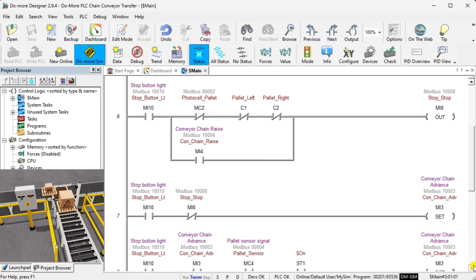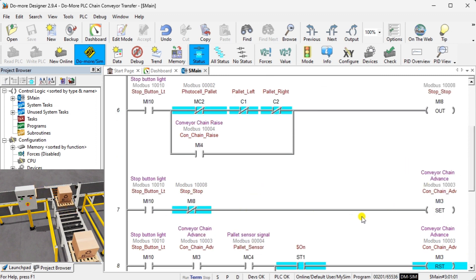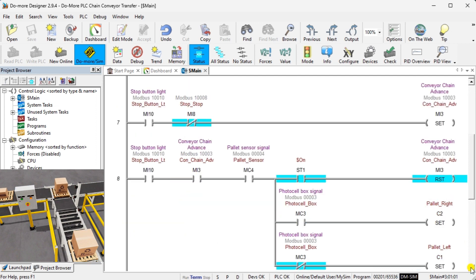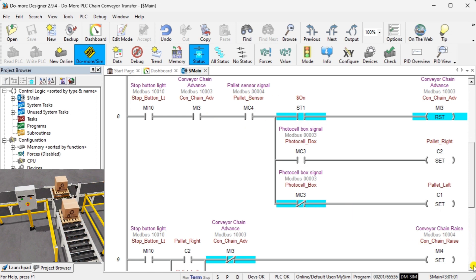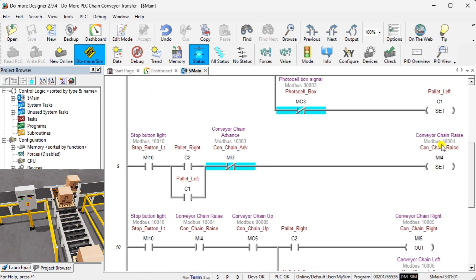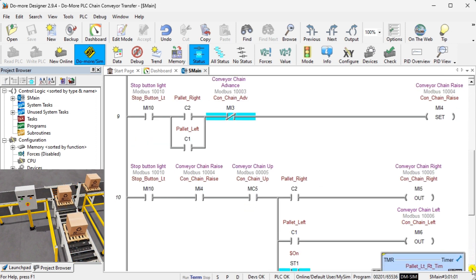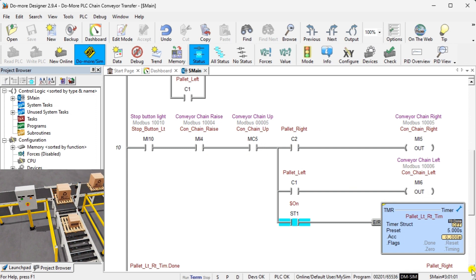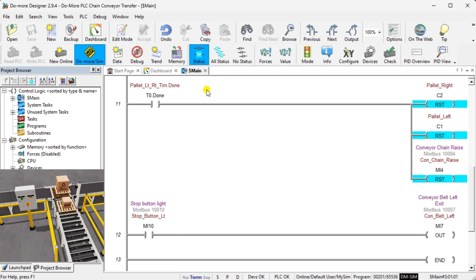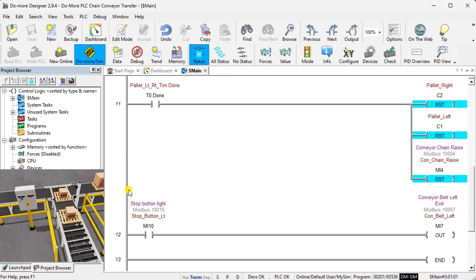The conveyor chain advance will bring the pallet into the chain conveyor. As the chain conveyor advances, the pallet sensor will activate. This will reset the chain conveyor advance and set the left or right pallet bits, depending on the photocell box sensor. Once it has been determined if the pallet is moving right or left, the conveyor chain rises. When the conveyor chain rises input is on, the pallet will move left or right and start a timer timing for five seconds. This timer is used to allow the pallet to move off the conveyor chain. At the end of the five second timer, the pallet rise and left and right bits are reset. The conveyor belt on the left and right will be on when the machine is running. This is the end of the program.